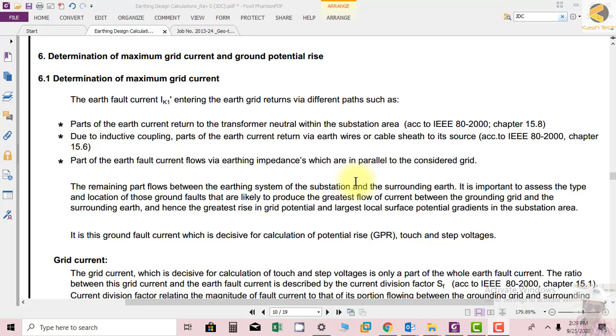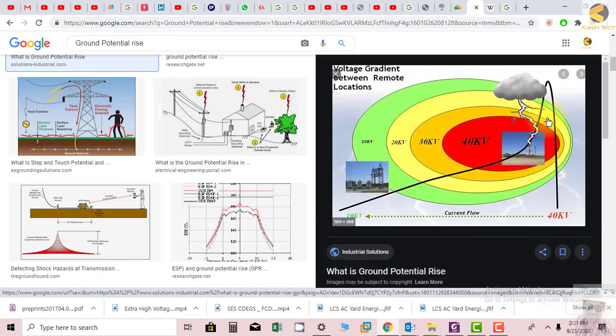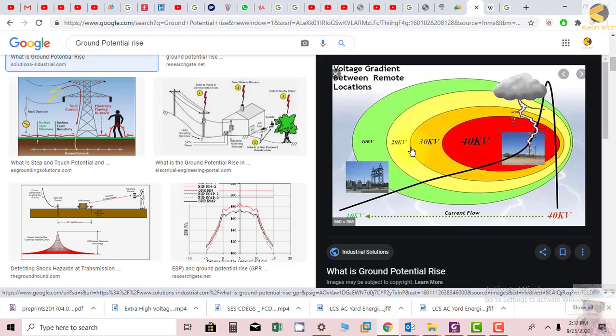It is important to assess the type and location of ground faults likely to produce the greatest flow of current between the grounding grid and surrounding earth, hence the greatest rise in grid potential and largest local surface potential gradient. For example, when a 40 kV conductor falls to ground, the ground potential at the fault point is 40 kV, reducing to 30 kV, 20 kV, 10 kV further away.